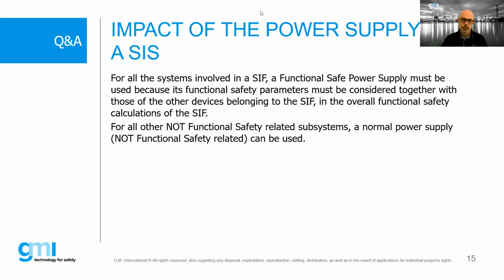Yes. And our experience with the safety relays for machines is that they are completely different. But I would say that for machine safety there are no specific functionalities except the reliability and the safety of the power supply. So, of course, power supplies must assure power for a long time without stopping, and protect the machine from unwanted overvoltage or low voltage. So I would say that it could probably also be useful for machine safety applications. Yes, but maybe also in this case, we ask you to send us your details, because you are anonymous and we don't see your emails. We want to give a proper, more detailed answer.